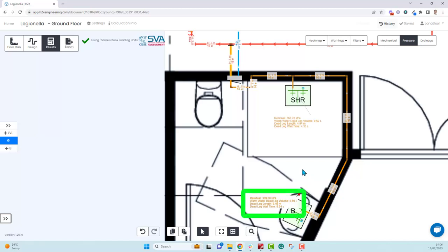It's only had a minimal effect on the pressure - we've lost around 5 kPa, so now we have 369.68 kPa. So it is well worth doing if your project has enough pressure, and of course you want to stay inside the limits of the standards for velocities and pressures.